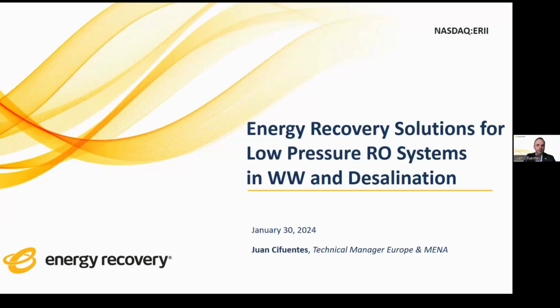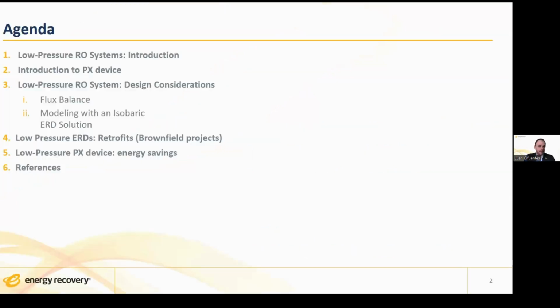So we're going to talk about energy recovery solutions for low pressure reverse osmosis systems in wastewater and desalination. The agenda is: an introduction about low pressure reverse osmosis systems, an introduction to the PX pressure exchanger device, how we can design low pressure reverse osmosis systems with the PX, what kind of retrofits we can do with these ERDs, these energy recovery devices, which energy savings we can achieve in low pressure systems, and a couple of references that have already been done.